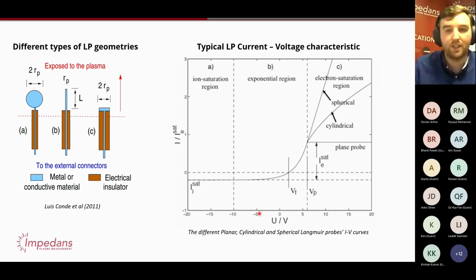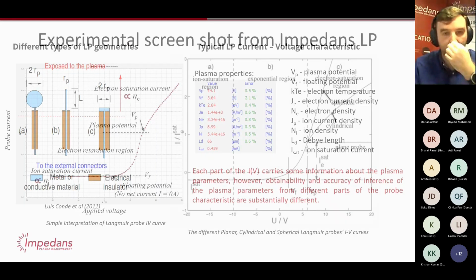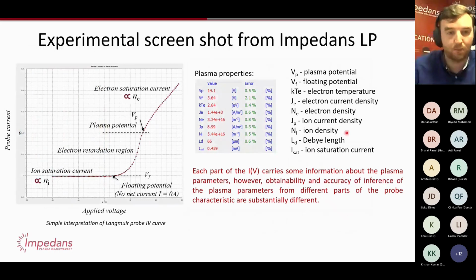Now this is just an example piece of data. This is also to show that the different probe types actually behave differently after a certain point, which is essentially to do with how the probe interacts with the plasma. The different shapes expand the sheath. But we'll get into that. Here's a screenshot from our commercial Langmuir probe, to show you an example of real data. You can see there's the ion current saturation region, this transition region, and then you get into the electron saturation region. Because this is a cylindrical probe, at that point you get this curve upwards as you apply higher and higher voltages.